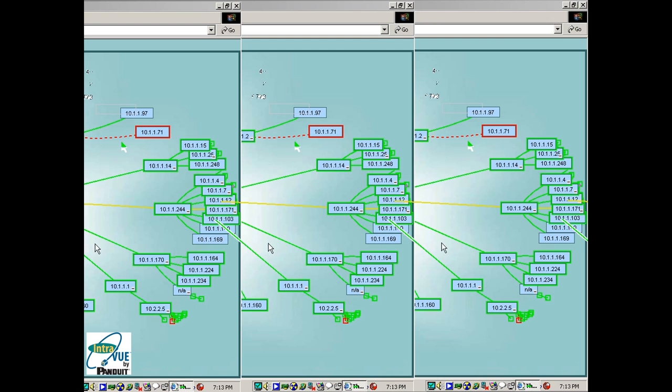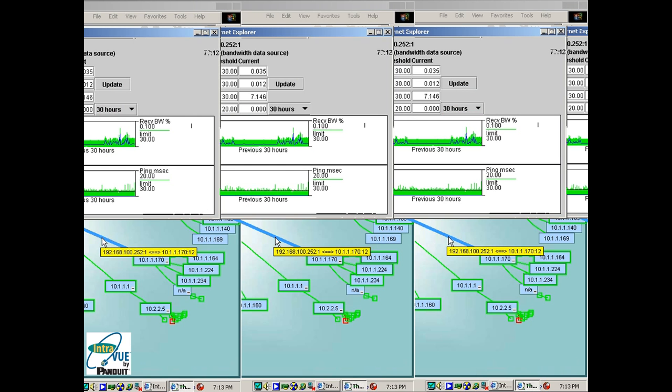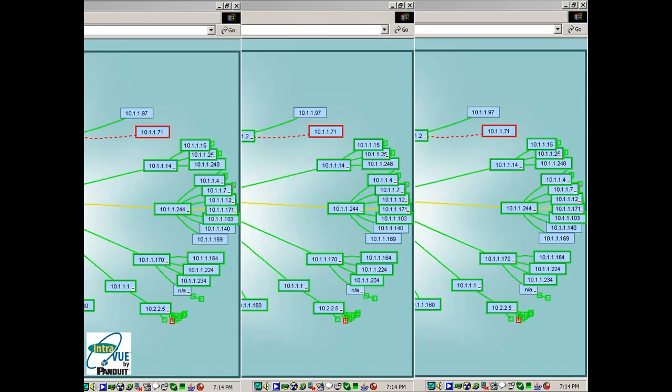This is a very important data point in finding connection problems, such as loose connections or ground faults, or if the communication module is becoming overloaded with other tasks or processor problems. The graphical view makes it easy for an individual to see not only the type of problem, but from the time-based nature of the view, can distinguish probable causes.